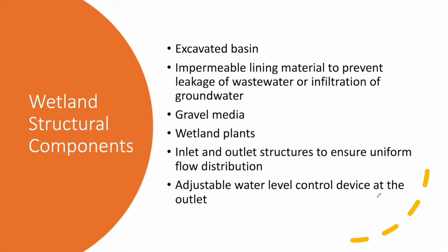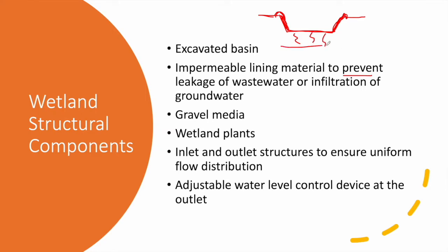The structural components of a wetland are simple. We need to excavate a basin that is sloped at the bottom. We then place an impermeable lining material — a geotextile and an HDPE membrane — which prevents leakage of wastewater and infiltration into the groundwater beneath the wetland.